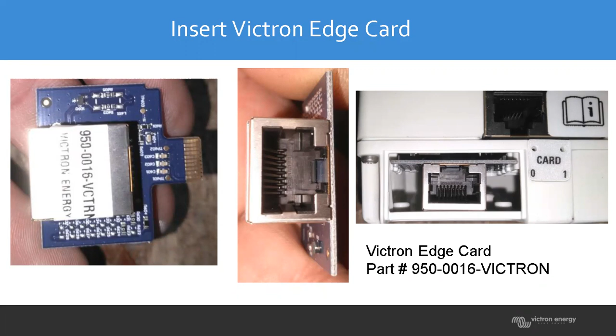All right, now we want to set up our comm. This is done via Cat5 cables. With this system, you'll need a DC power converter that gives power to the communications network. When you get a Discover battery, it comes with a splitter, an RJ45 splitter, placed in COM 2 of every battery you have. You're daisy chaining that in and out to the Lynk device, out of the Lynk device into your GX device, and then terminated.